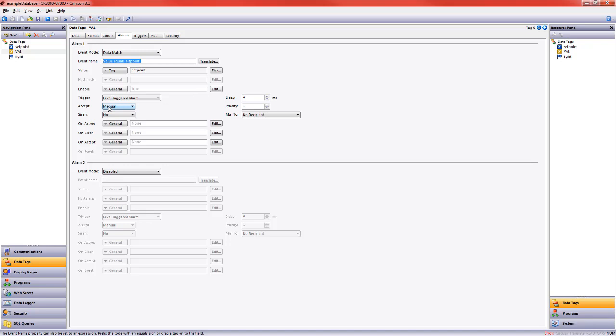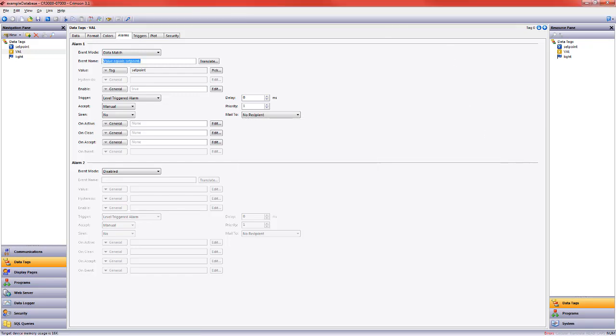I'm going to leave this as manual. Remember in the alarm primitive, we have that wait accept. So what happens is when this is true, it will be red. But if it's occurred and then hasn't been accepted or noticed by our operator, it'll stay on the screen, but it will turn gray. Let's go ahead and send this to our HMI.